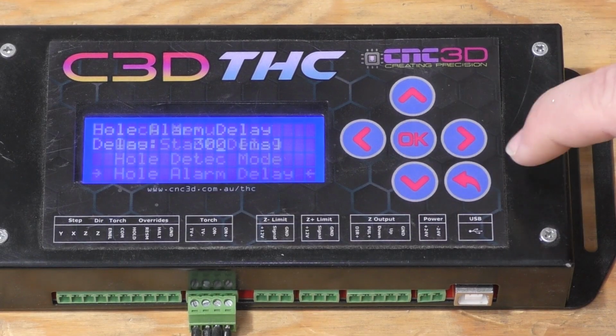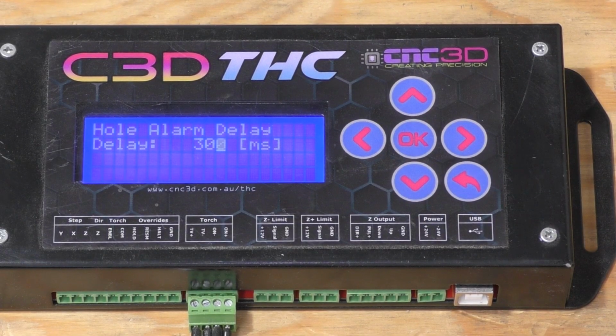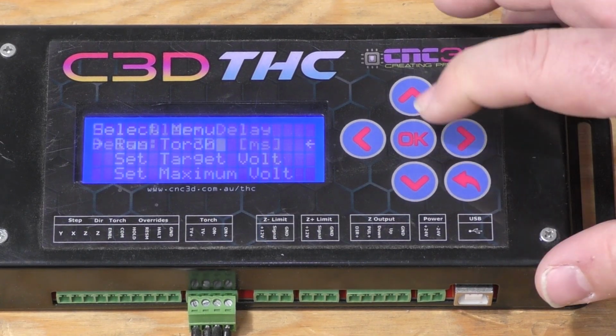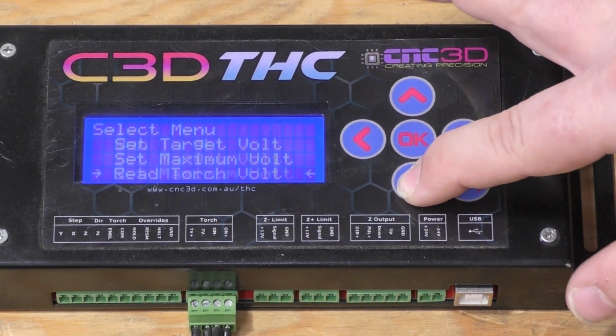Hole alarm delay, this is what we were talking about just before. Hole alarm delay is how long it will detect those high voltages for before it sends the alarm signal. So this is 300 milliseconds, that's a very short time, which is usually pretty good. Holes, you don't usually go over a hole and you want it to stop pretty quickly if it does. So 300 milliseconds is the time that I've got set here. And we'll scroll down to the next menu.